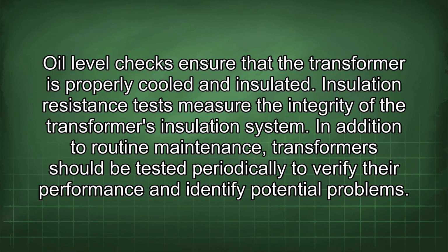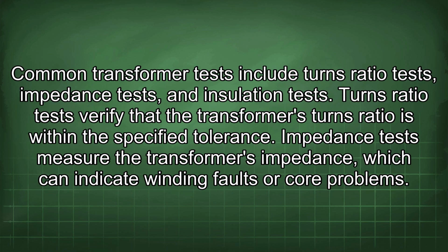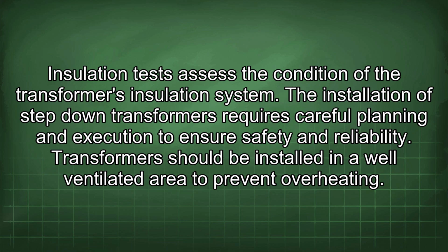In addition to routine maintenance, transformers should be tested periodically to verify their performance and identify potential problems. Common transformer tests include turns ratio tests, impedance tests, and insulation tests. Turns ratio tests verify that the transformer's turns ratio is within the specified tolerance. Impedance tests measure the transformer's impedance, which can indicate winding faults or core problems. Insulation tests assess the condition of the transformer's insulation system.